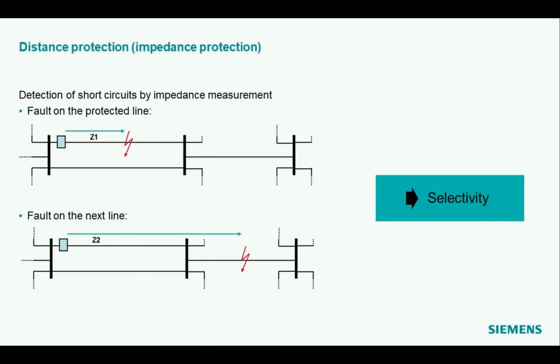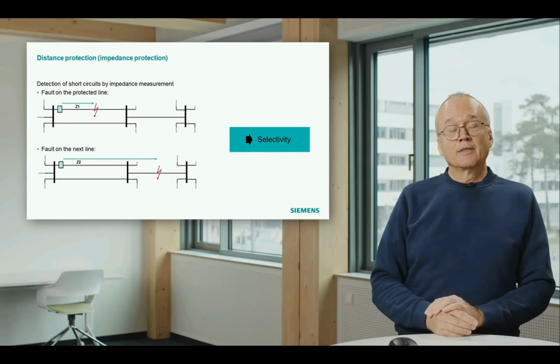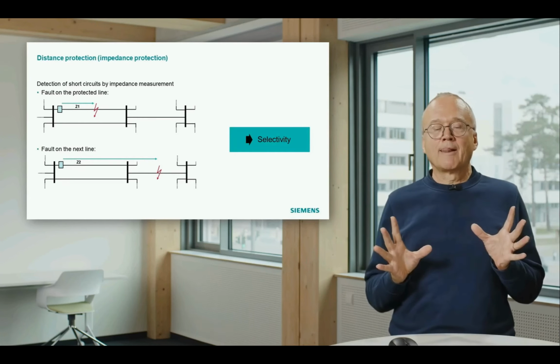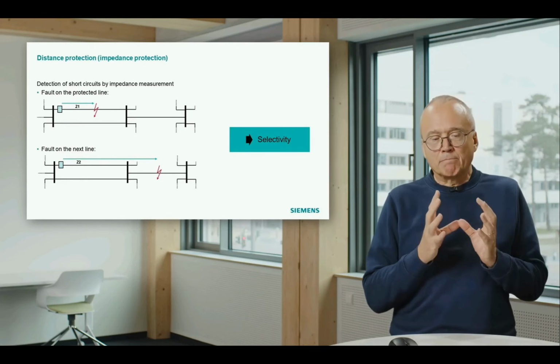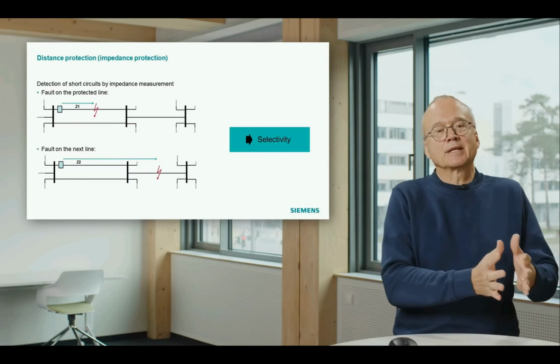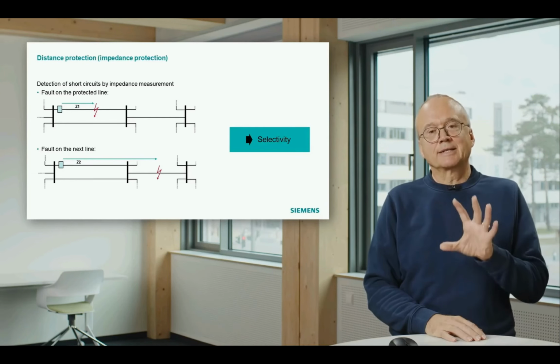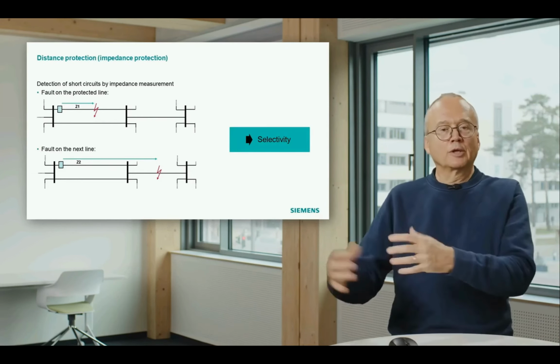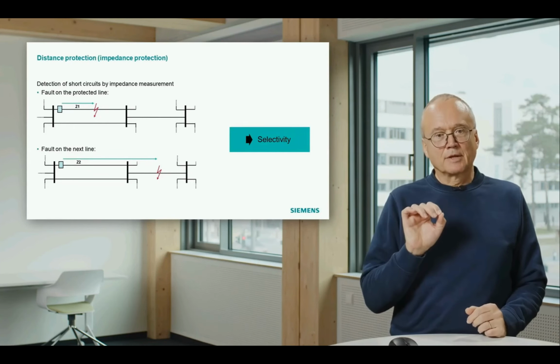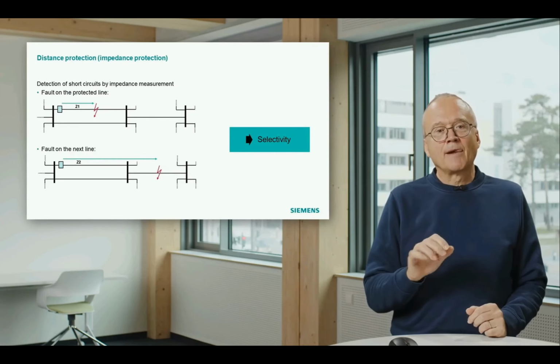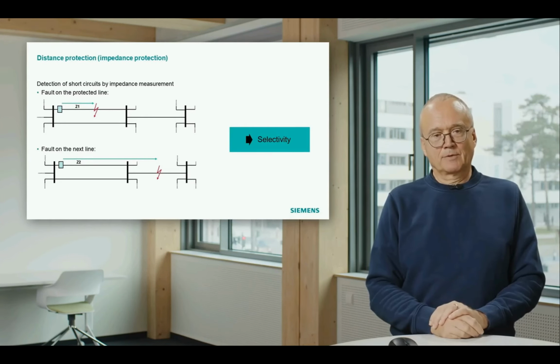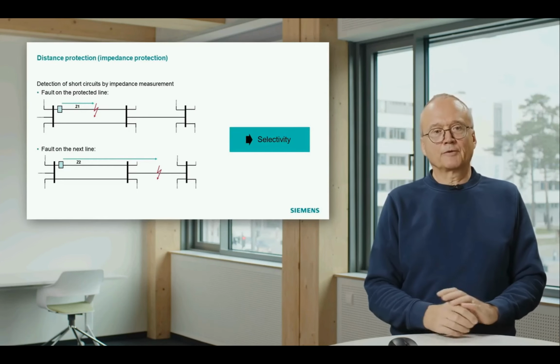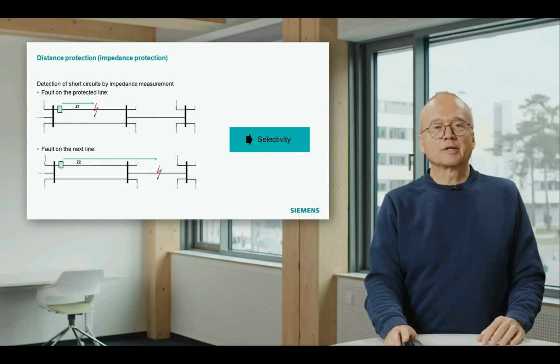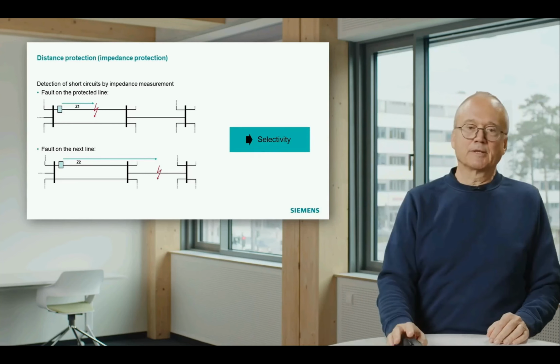And if you look at the lower part, where the short circuit is on the next line, it measures a larger impedance, an impedance which is higher than the impedance of the line. Then it says, okay, I see a short circuit somewhere, but it's not on my line. That means based on this comparison, measured impedance against impedance of the line, we can get a decision, fault on the line or fault somewhere else. That means with this, we can get selectivity without any delay times. And that is the advantage of distance protection. I already mentioned it's called distance protection, although it is based on an impedance measurement.